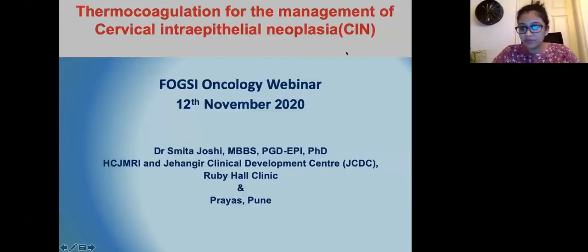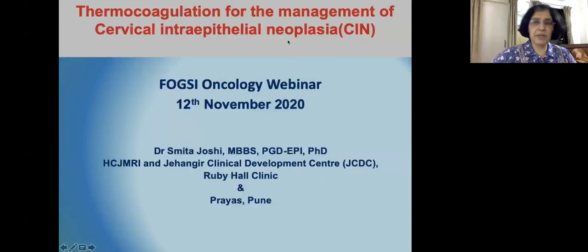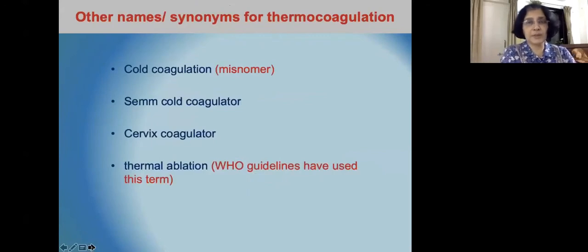So I will be speaking on thermocoagulation for the management of cervical intraepithelial neoplasia. Now, across the world, this terminology, thermocoagulation, is used interchangeably with other names as well. Thermocoagulation is also known as cold coagulation. It is in fact a misnomer because it is heat coagulation. It is also called the Semm cold coagulator. This is the terminology that was used by Dr. Kurt Semm way back in the 1960s. It is also called the cervix coagulator, and recently it is called thermal ablation, and WHO has acknowledged the fact that this modality uses ablative treatment, and therefore they have recommended us to use thermal ablation.